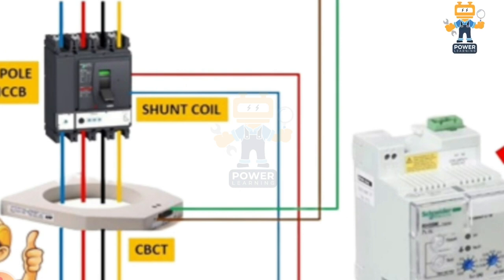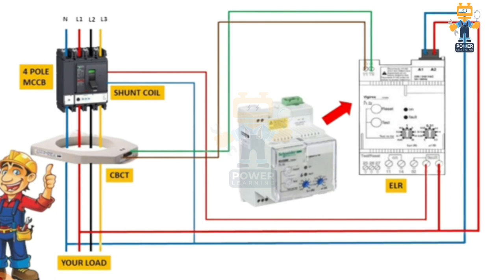The earth leakage relay will activate a switch. Here you can see these two red wires — they work as a switch contact. Once the CBCT signals the earth leakage relay, the relay closes this contact. This closed contact commands the shunt coil located inside the four-pole breaker. The blue wire connects directly to the shunt coil, so once the earth leakage relay is activated, it triggers the shunt coil, which trips the breaker and protects the circuit.